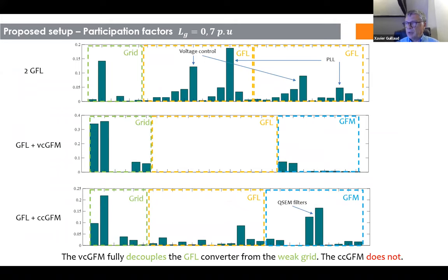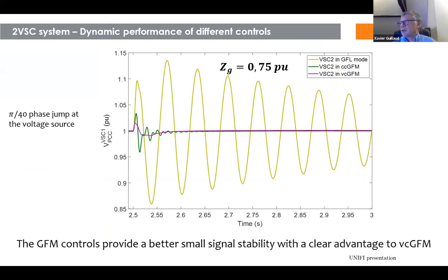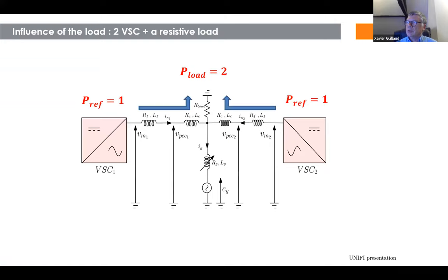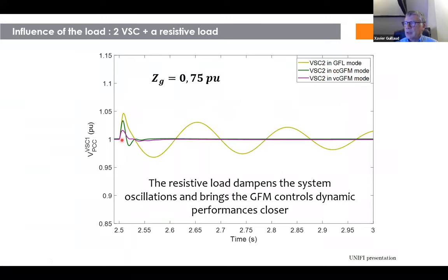Simulation results at the stability limit confirm: grid-following is unstable, VCGFM is very stable, and CCGFM is at the boundary. We also applied a π/40 phase jump at the voltage source. Adding a resistive load damps the system as expected, and in that case the behaviors of VCGFM and CCGFM are closer together — the resistive load tends to bring the two GFM control dynamics closer.